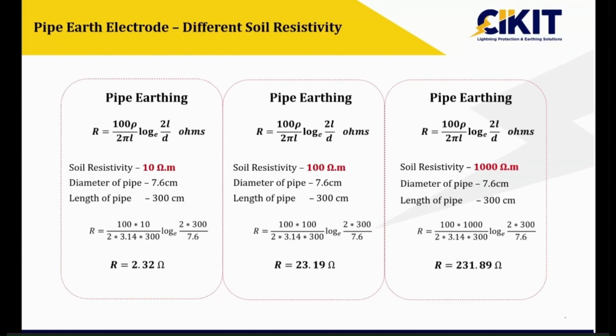This is just a comparison of the earth resistance value for different soil resistivities. In the first case, we have 10 ohm meter. For the same earth electrode, a pipe of 76 mm diameter and 3 meters long, the resistance value will be 2.3 ohms. If I go for 100 ohm meter, the value will be around 23 ohms. If I go for 1000 ohm meter soil, it will be 231 ohms.